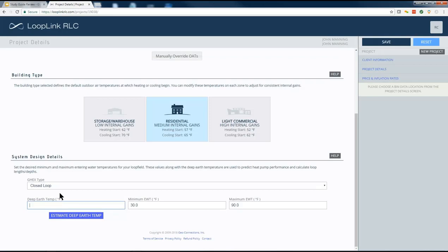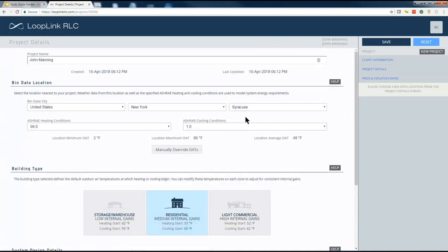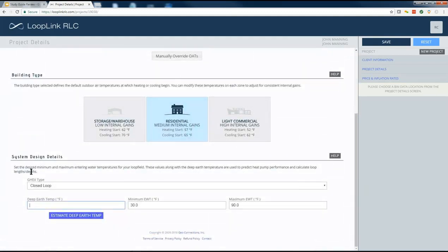And then the very last thing that you need to do is specify your ground loop design parameters. Generally speaking, 30 degrees minimum, 90 degrees maximum are default values for most programs. Specify your deep earth temperature. Generally speaking, if you aren't sure what it is, you can usually estimate it to be a few degrees above the average air temperature for the bin data location that you've specified. You'll notice that we've actually got a little button here that'll calculate it for you based on the bin data that you've loaded up in the program. So I'll go ahead and click that button. It'll think for a minute and notice now that it estimated the deep earth temperature to be about 52 degrees.